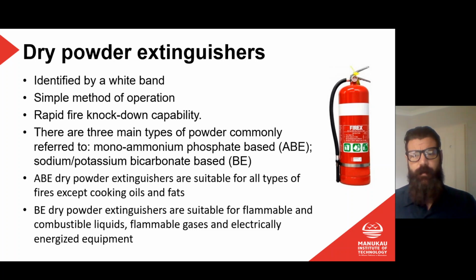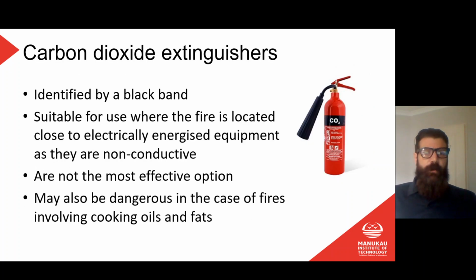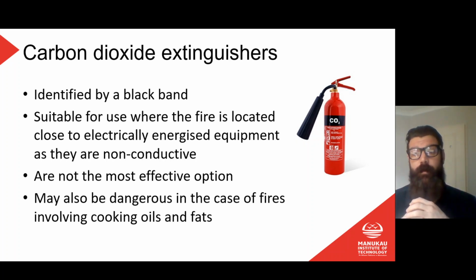You certainly don't want to be breathing it in, and then once you're finished with it, you've got to get rid of it all, and it is an absolute nightmare to clean up. It sticks. It's very, very fine dust and powder. It's quite sticky, very hard to remove. So if you're going to spray that inside a switchboard, you might end up rebuilding that switchboard. Carbon dioxide, so it's identified by a black band, suitable for use where the fire is located close to electrically energized equipment as they are non-conductive. So the carbon dioxide is not going to create a hazard by conducting electricity when we spray it.